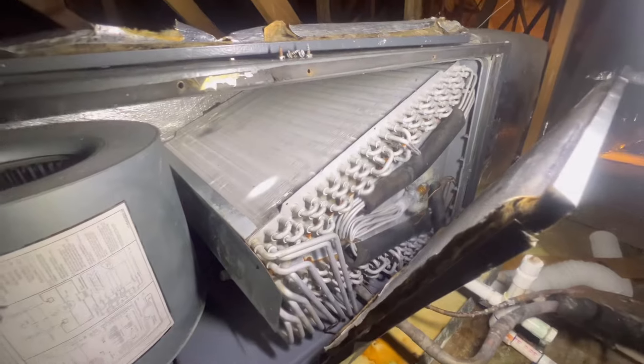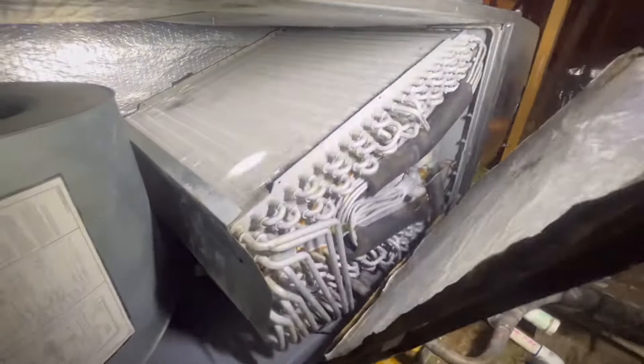Alright guys, so this is your evaporator coil. Like I said, this is the return side — the air is going to come from the space, come through this coil, heat is going to be removed, and the cool air is just going to go to the supply side for the other rooms. This is an A-coil right here — I think it's aluminum. Yeah, looks like it's aluminum.